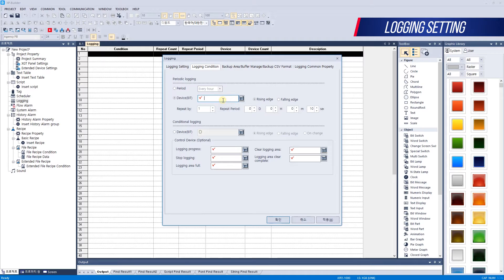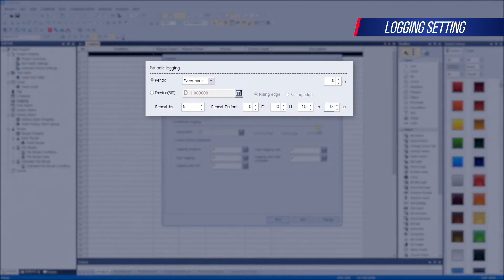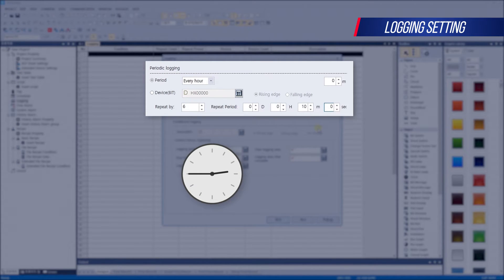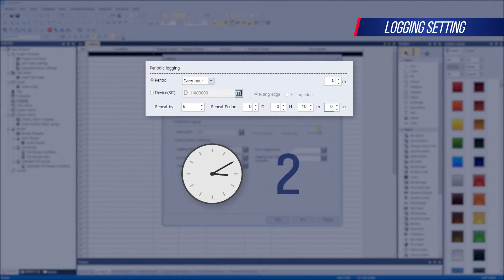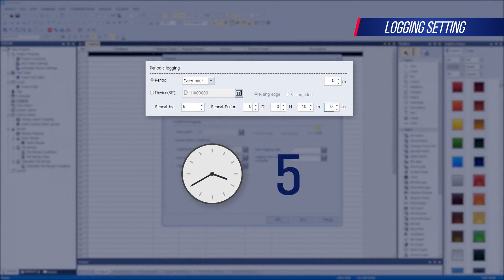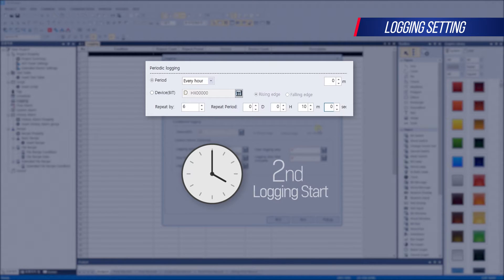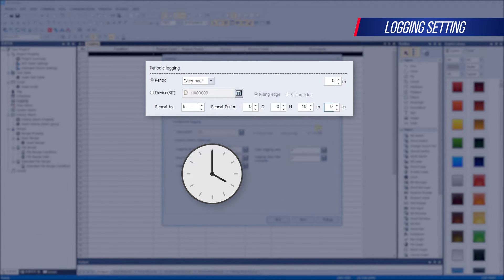It can also be set to when the bit device rises or falls. Let's make a logging that starts every hour and repeats every 10 minutes. If the current time is 2:45, logging starts at 3 o'clock, which is the set time of every hour. Perform the first logging at 3:00, the second at 3:10, the third at 3:20, the fourth at 3:30, the fifth at 3:40, and the sixth at 3:50. Then the second logging starts at 4 o'clock, and logging operates a total of 6 times every 10 minutes. You can set a maximum of 255 iterations.